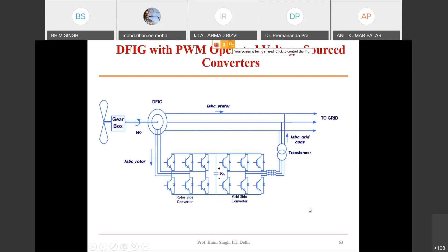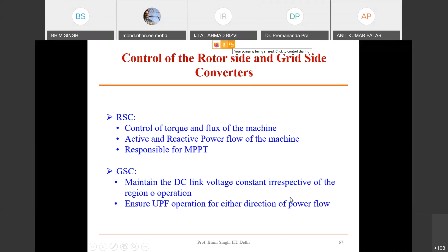We have limited time already. You have a rotor side converter, which is responsible for control of flux of the machine and active and reactive power control. By active power control we do MPPT, that is responsible for torque or speed control, and the reactive power control is to make the power factor of the stator unity. That is the rotor side converter control. As far as the grid side converter is concerned, you have to maintain the DC link voltage by active power, and you maintain unity power factor, that is, reactive power control on the grid side. So if the grid needs some reactive power, required for the transformer or so, you do that with the help of this converter. So you have an inner current control loop, the rotor current, and an outer control loop.